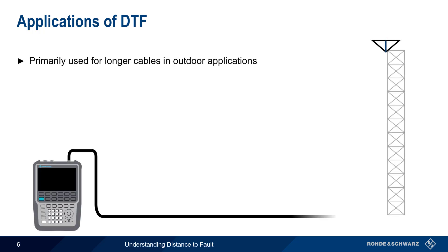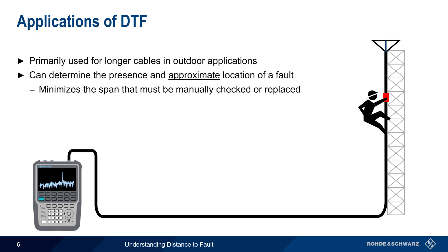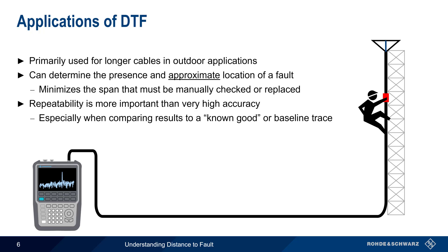Distance to fault is primarily used for longer cables, often outdoors, such as the feeder cable of a tower-mounted antenna. DTF can determine both the presence and approximate location of a fault — that is, it minimizes the section of cable that needs to be manually checked or replaced. Repeatability of the measurement is often more important than extremely high accuracy, which is difficult to achieve in practice. For example, we often want to compare a current measurement to a known good or baseline trace.